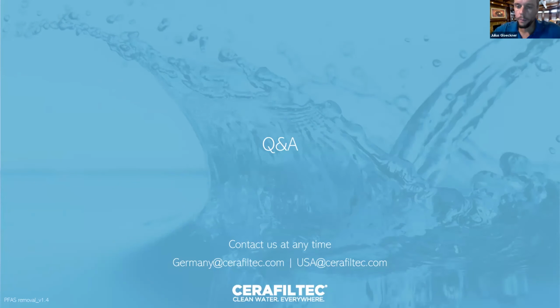So let's say 12 hours later, we do a backwash, everything washes down. As Chris said, this very limited amount of waste then gets washed out, and we bring a new powder activated carbon layer onto the membrane. And the key here in this entire equation is that because of this high adsorption effectiveness and efficiency of powder activated carbon, in total, we use less unit of weight, or less carbon, than a GAC would to remove the same PFAS. Right? So yes, we bring a new layer on every 12 hours, but it is so thin, a fraction of a millimeter effectively, right? And we replenish it, but in total, we have less carbon used over the course of the year.